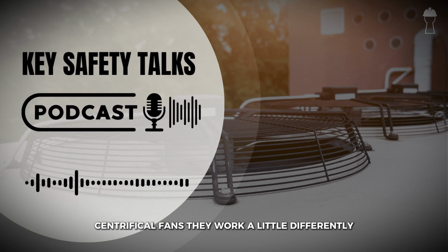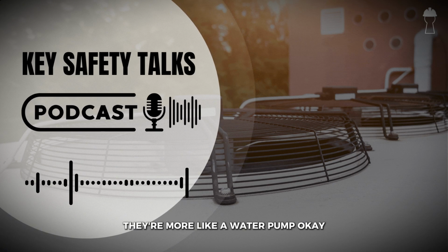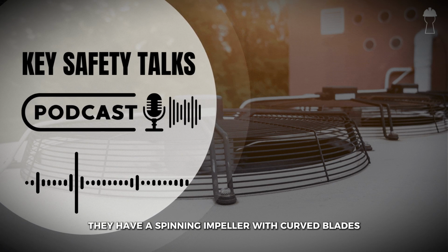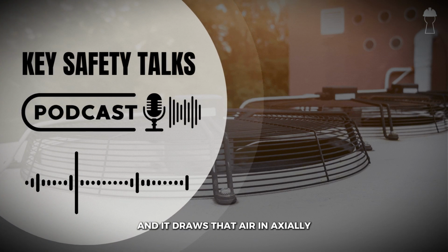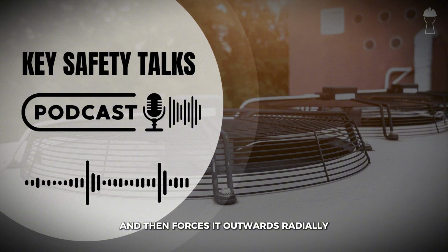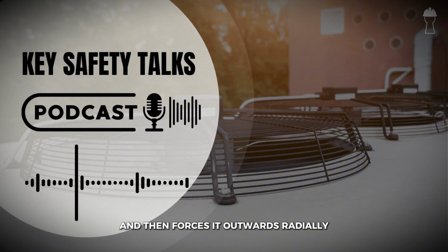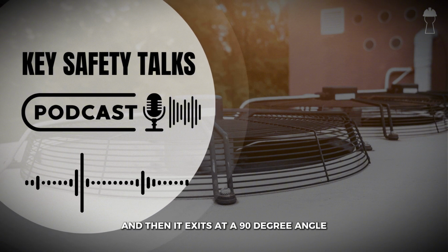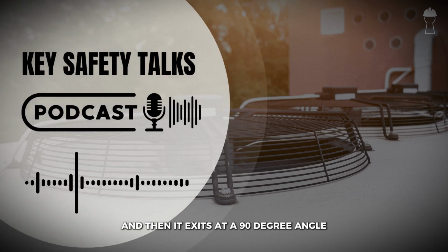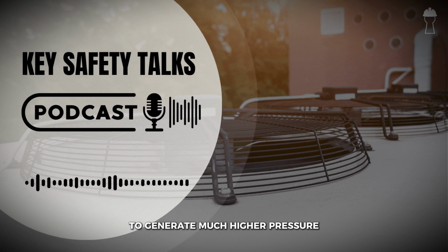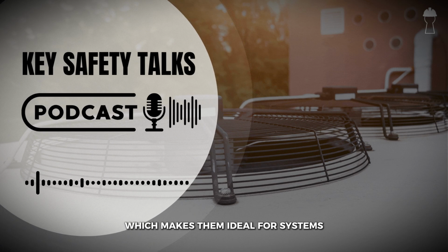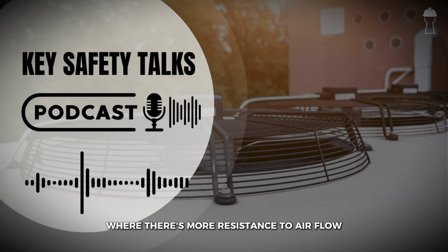Exactly. Now, centrifugal fans, they work a little differently. They're more like a water pump. Okay. They have a spinning impeller with curved blades, and it draws that air in axially and then forces it outwards radially. So the air enters along the axis, and then it exits at a 90-degree angle. You got it. And this design allows centrifugal fans to generate much higher pressure, which makes them ideal for systems where there's more resistance to airflow.